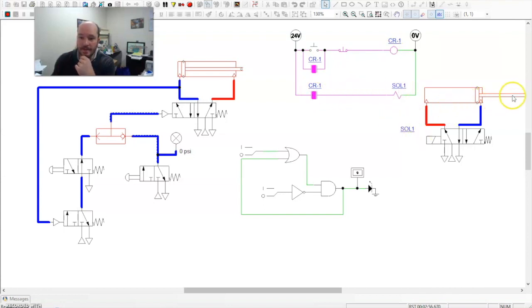That coil is also latched in a second set of contacts that activate solenoid one, and the cylinder extends. Now, to stop this, because this is a spring return, all I have to do is hit the stop button here. When I hit the stop button, that turns off the power to the coil, opening the switches that were closed because of the electromagnet. That turns it off, and this returns it.